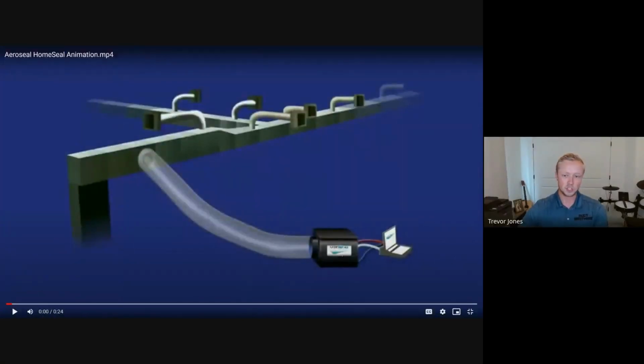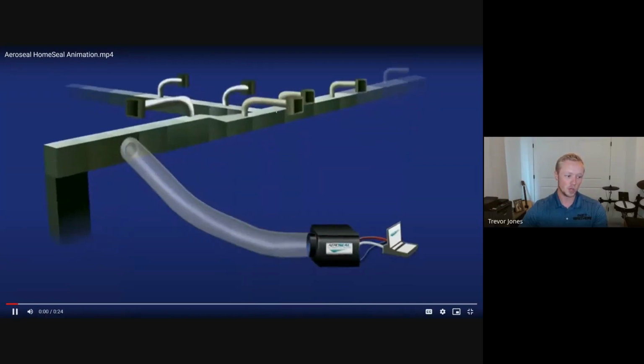This machine here is what we call the fan box. We use it to pressurize the duct system. Normally this is all encased in the attic or in the walls, depending on the home. But we can access it at the furnace, and we block off all the air vents with foam plugs so none of this glue comes out into the home, which allows us to pressurize the system. So we hook everything up.